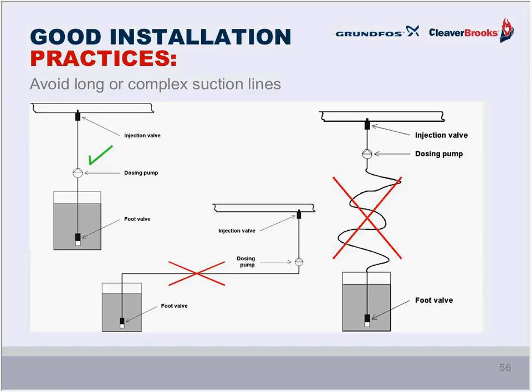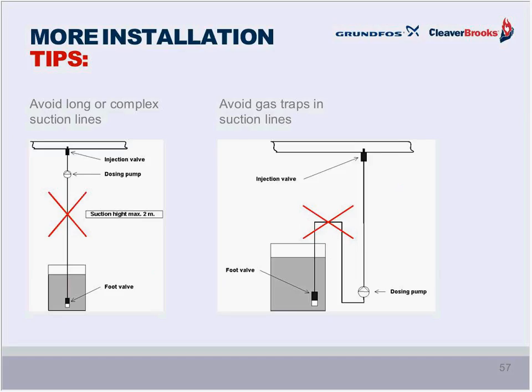To prevent cavitation problems, keep your lines as short and straight as possible, and do not exceed the liquid suction side lift recommended by the pump manufacturer. And please do not create peaks and valleys in your suction line. This will cause all sorts of headaches with startup, things like that. I've heard that many times, and most of the time it was the poor practices. So keep that in mind. Otherwise, you get the gas or vapor lock, and it's tough to actually move the liquid. So, things to be aware of.